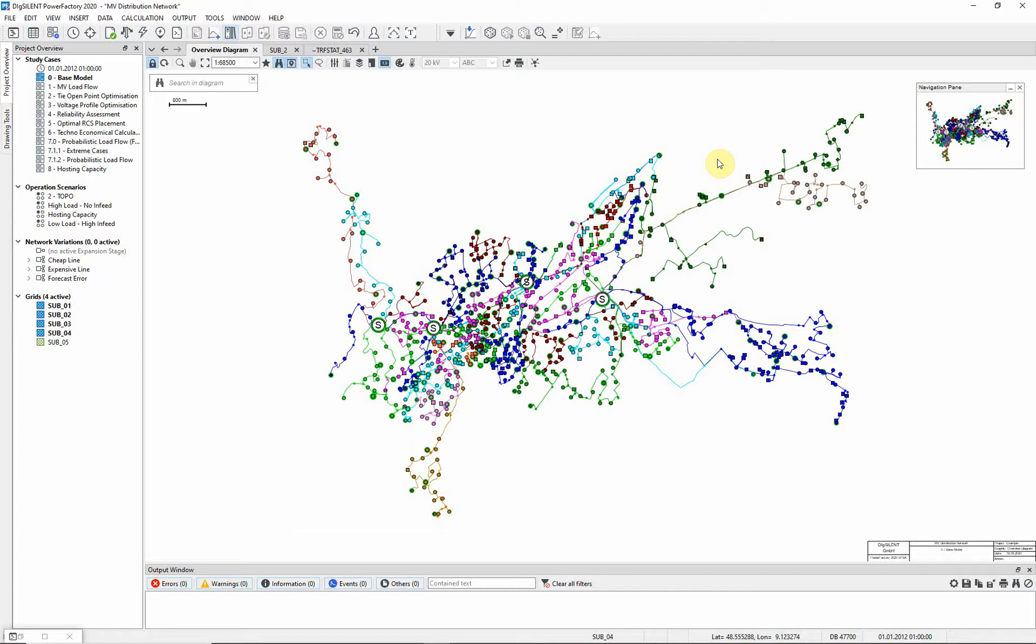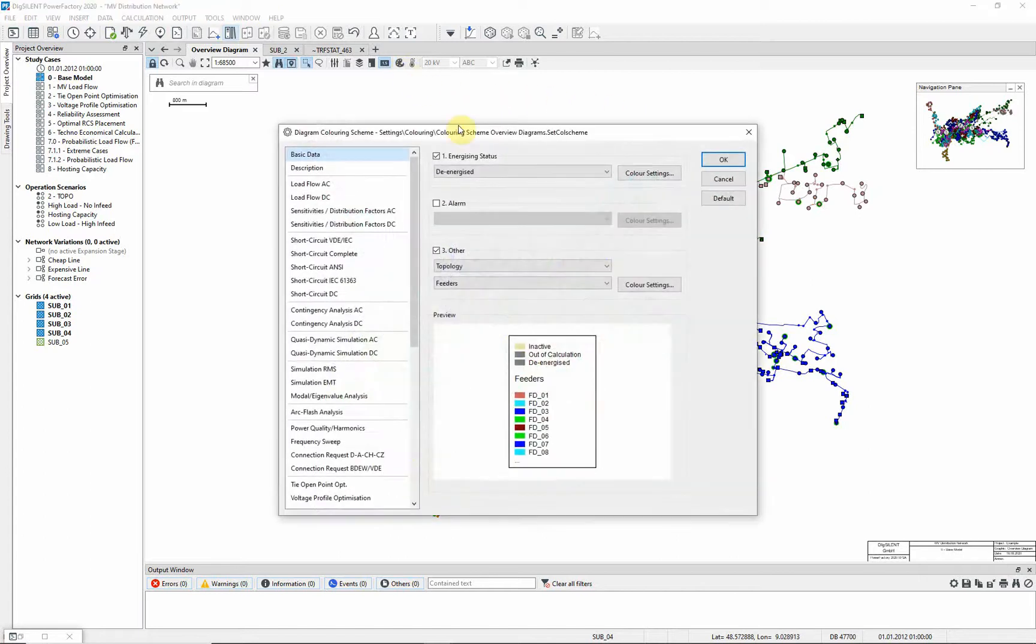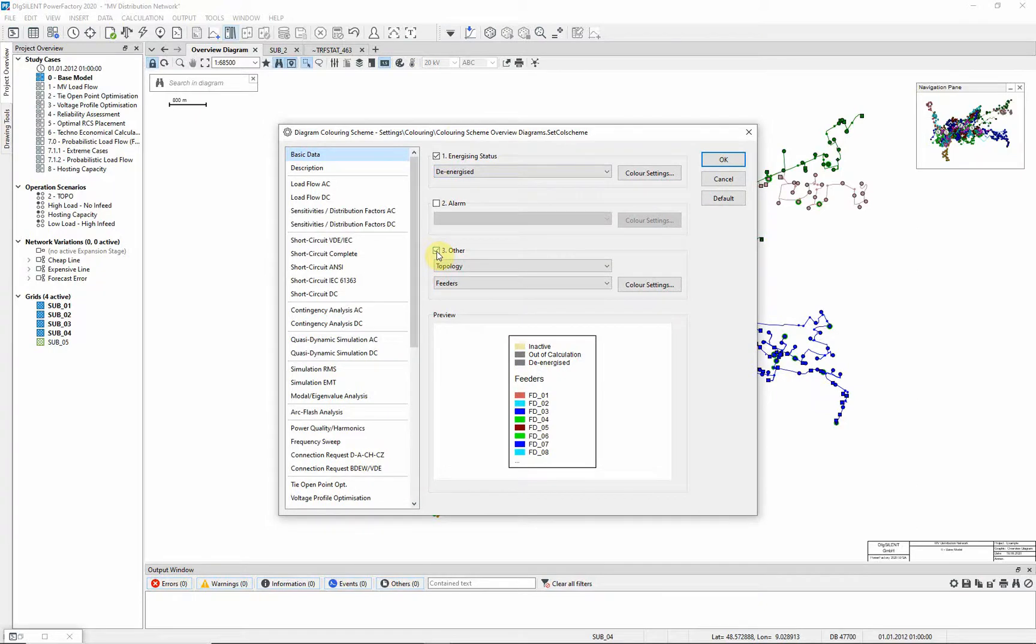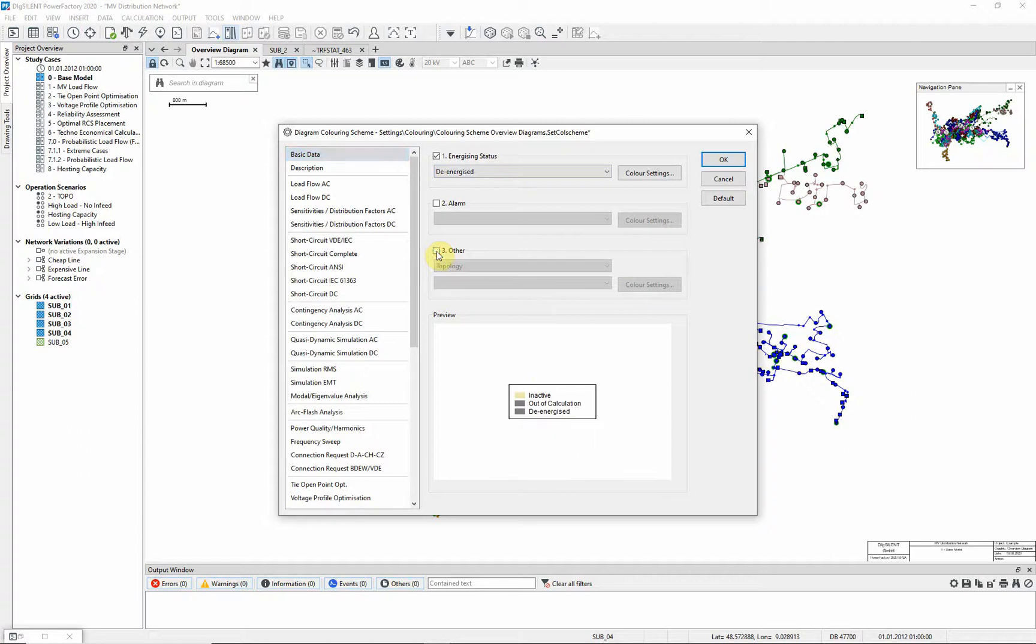Suppose we are concerned that feeders that should be operating radially are actually operating in a ring. We can activate a coloring alarm feature, which will highlight such cases. First, to make things easier to see, the feeder topology coloring will be deselected. The option alarm is selected, and feeder radiality check.